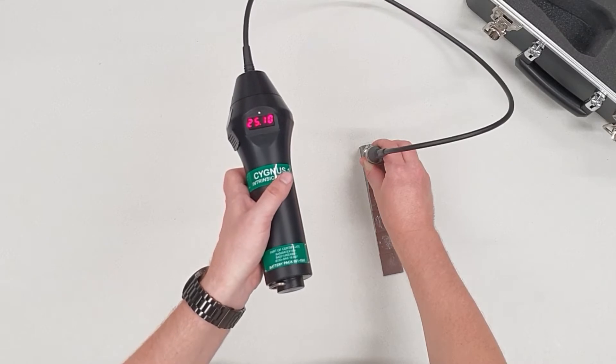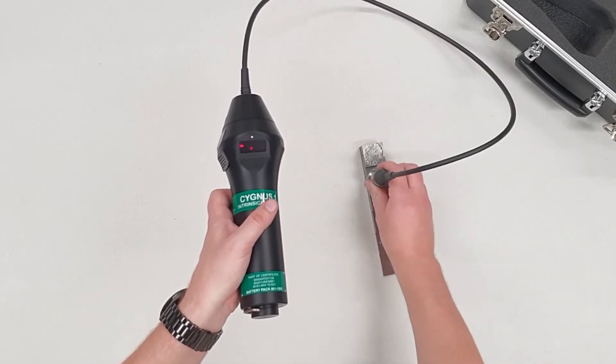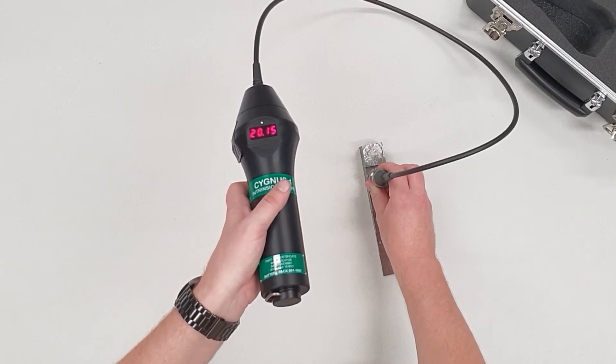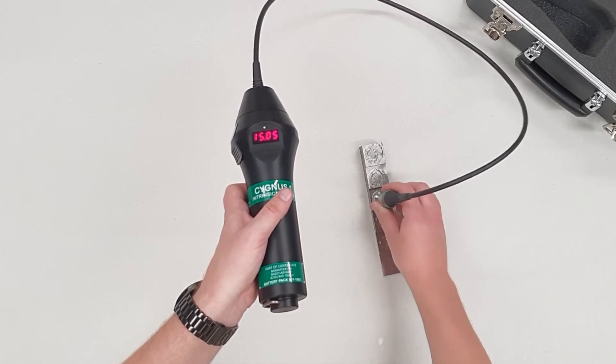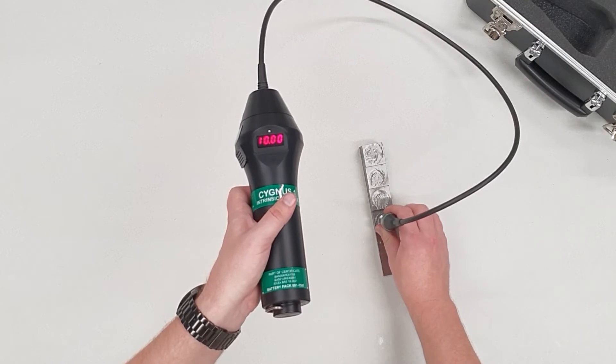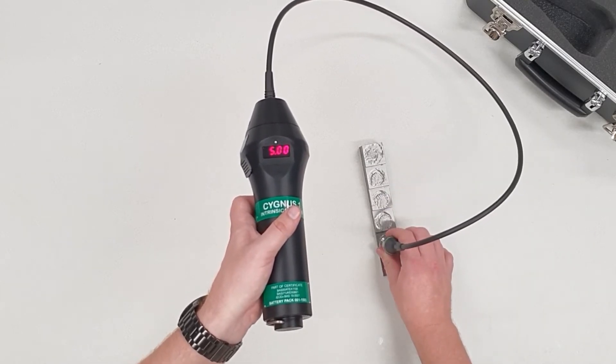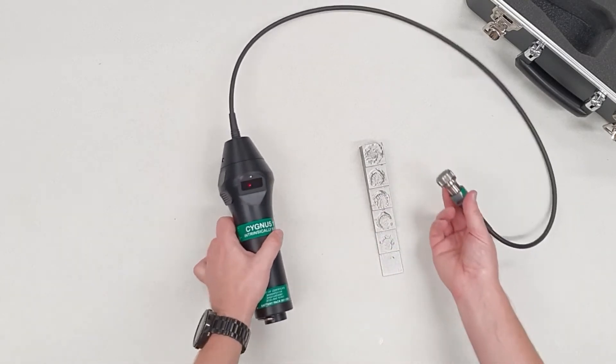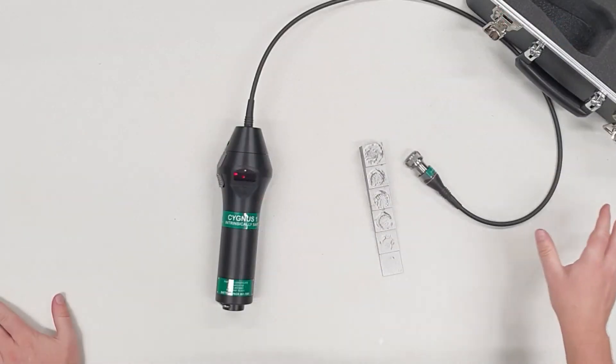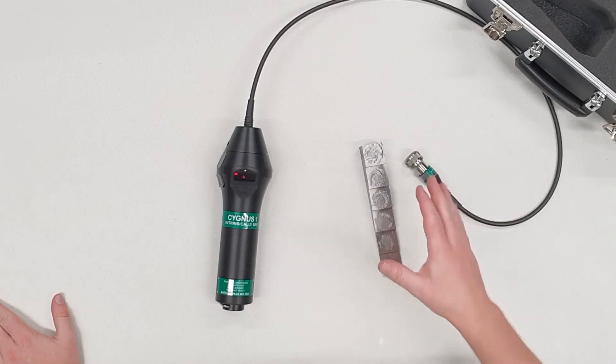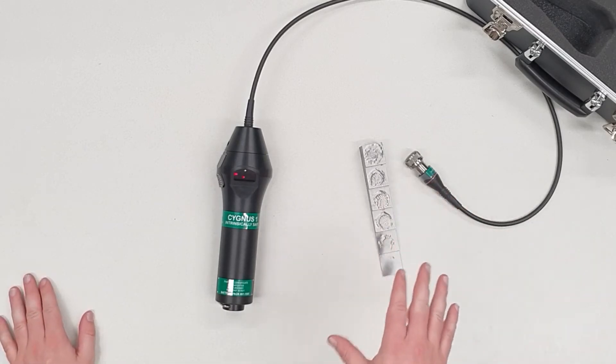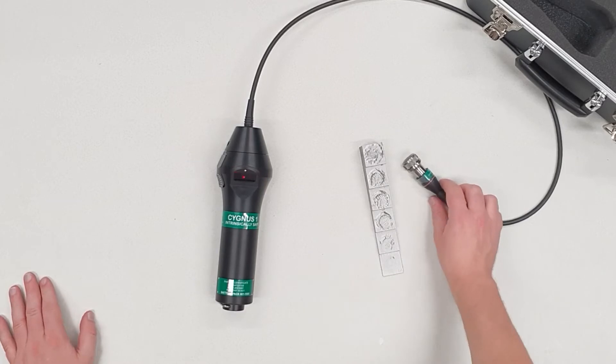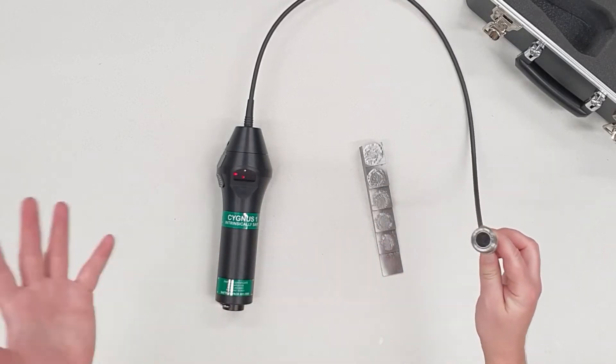Here I have a step wedge. The sound travels from the probe into the part, down, hits the back wall, echoes back and measures the response time, converting that to thickness. At the moment it's reading 25.1 mm. Next block down is 20, 15, 10, and 5. The couplant is water washable, very easy to remove, but it's very important that you use it. If you don't use any couplant, you won't get a reading. The same principle applies with the membrane. If you've got air trapped under the membrane, it's the same.